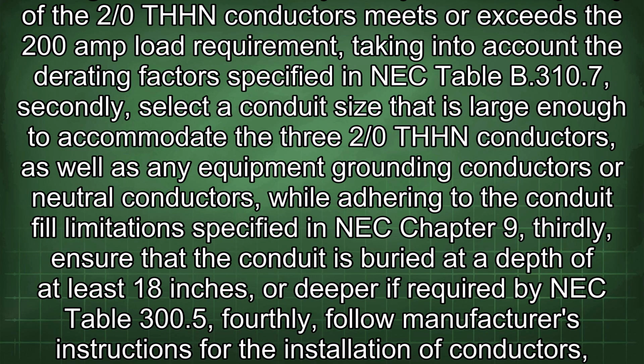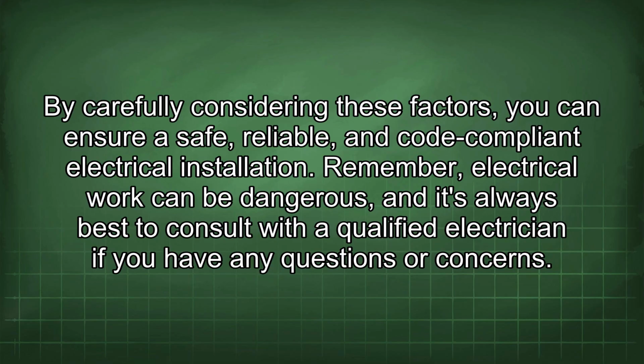Thirdly, ensure that the conduit is buried at a depth of at least 18 inches, or deeper if required by NEC Table 300.5. Fourthly, follow manufacturer's instructions for the installation of conductors, conduit, and other electrical equipment. And fifthly, obtain an electrical inspection to verify compliance with all applicable codes and regulations. By carefully considering these factors, you can ensure a safe, reliable, and code-compliant electrical installation.